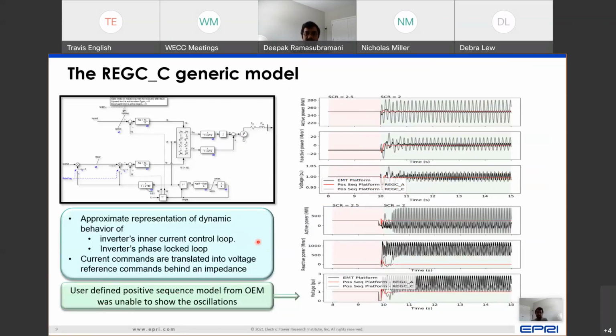And it can be tuned to provide a much more accurate representation of the dynamics of these fast control loops in the inverter. And with that, you can see that here, when you compare it against an EMT domain black box model obtained from the manufacturer, the EMT domain model showed oscillatory behavior when the short circuit ratio went from 2.5 to 2. The REGC_C model is also able to show a representation of the oscillatory behavior, though not at the same peak-to-peak value, but it's sufficient for a system planner to know that, hey, something is going on in the system and we need to investigate this further, as compared to the existing REGC_A model that didn't show any oscillatory behavior at all.